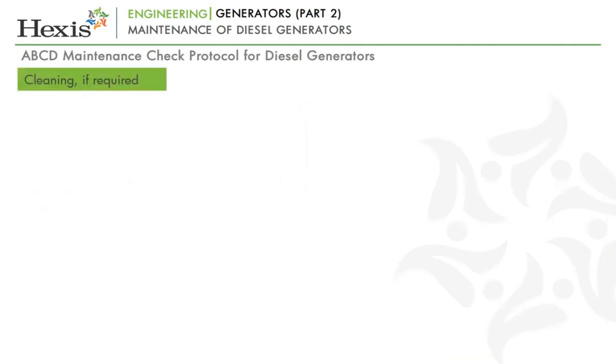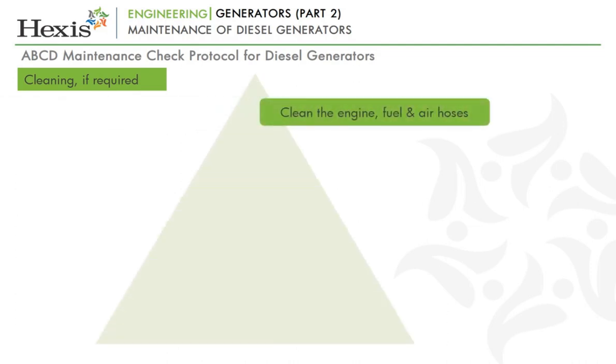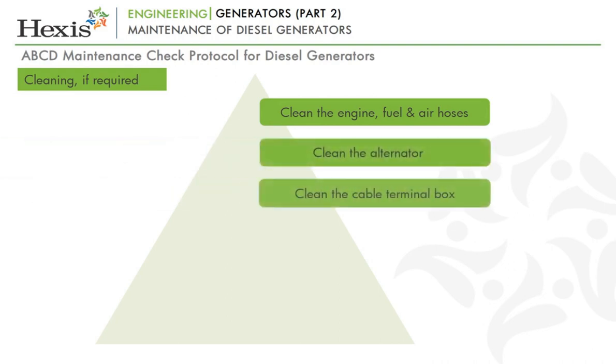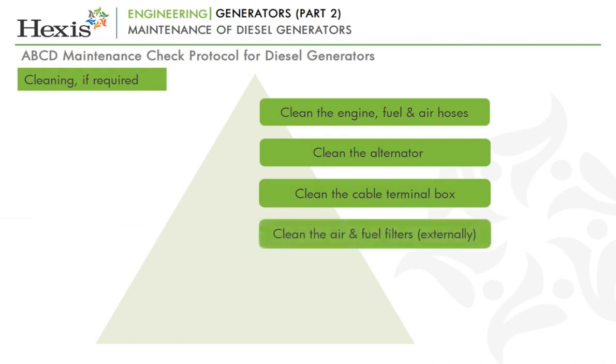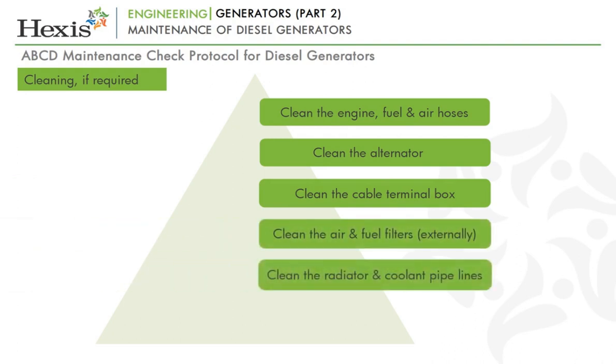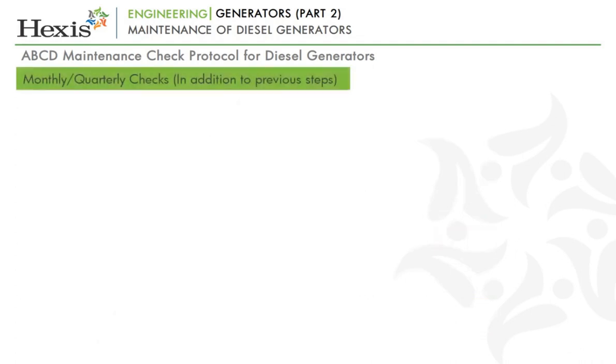Now, let's look at the following DG parts that must be cleaned. Clean the engine, fuel and air hoses. Clean the alternator. Clean the cable terminal box. Clean the air and fuel filters externally. Clean the radiator and coolant pipelines. Clean the batteries and cables. Let's now look at the monthly or quarterly checks which are in addition to above.